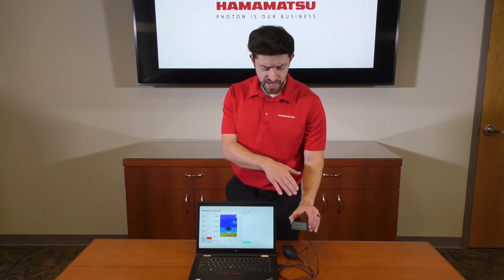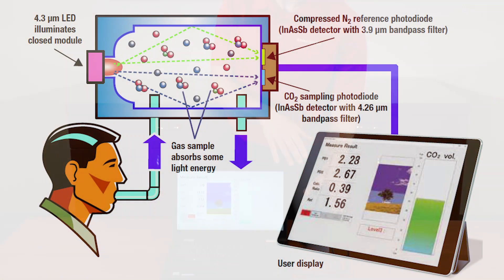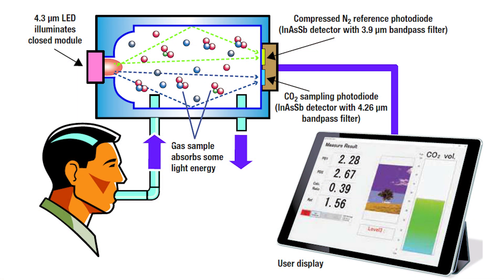So what's going on inside this little gas detection module? Well, first there's a 4.3 micron LED. Why 4.3 micron? That is a very strong absorption band for carbon dioxide. And then we have a couple of InAsSb diodes, each with a bandpass filter. The first bandpass filter is centered at 4.3 — that is the measurement channel. The other diode is the reference channel, centered at 3.9.